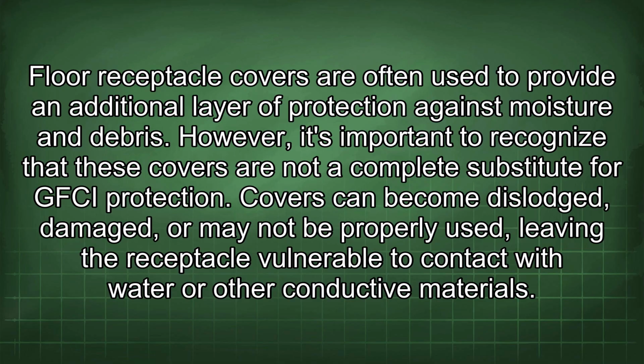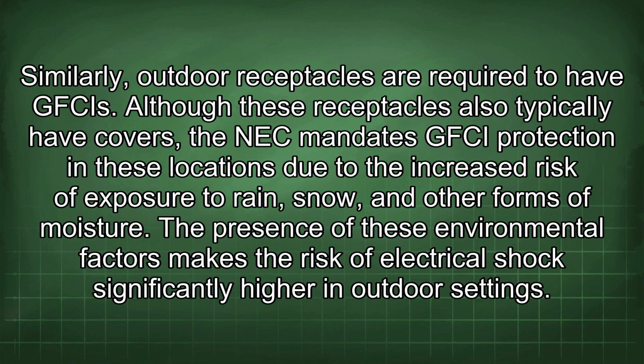Floor receptacle covers are often used to provide an additional layer of protection against moisture and debris. However, it's important to recognize that these covers are not a complete substitute for GFCI protection. Covers can become dislodged, damaged, or may not be properly used, leaving the receptacle vulnerable to contact with water or other conductive materials. Similarly, outdoor receptacles are required to have GFCIs. Although these receptacles also typically have covers, the NEC mandates GFCI protection in these locations due to the increased risk of exposure to rain, snow, and other forms of moisture. The presence of these environmental factors makes the risk of electrical shock significantly higher in outdoor settings.